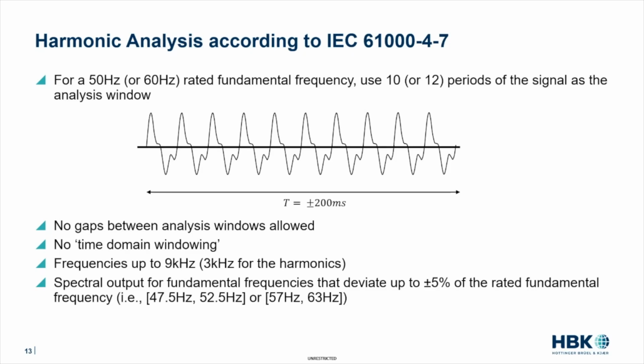And of course, if you look at power grid signals, we are normally talking about nominal frequencies of 50 hertz or nominal frequencies of 60 hertz, but of course in real life those frequencies are never exactly 50 hertz. So if there is a very big load on the total power grid, your frequency will be slightly lower than 50 hertz, and if your power grid is only very lightly loaded, maybe during the night or something, then your frequency will be slightly higher than 50 hertz, but it's always in the order of 50 hertz.